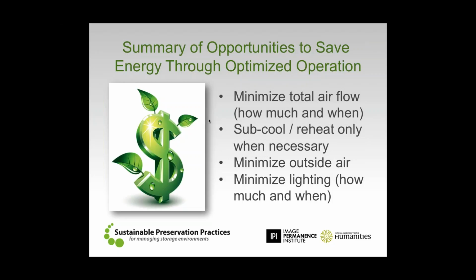A big one, looking both at energy and at preservation quality, is making sure that you minimize the outside air. We keep materials inside of the building and try to control the environment specifically because the outside air conditions most of the time aren't conducive to long-term preservation. So don't bring in any more of that outside air than necessary. It's more work for the system to do, and the more work that the system has to do, the greater the potential that more of that energy is going to get into the storage space where you don't want it.